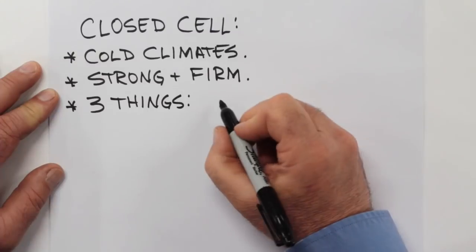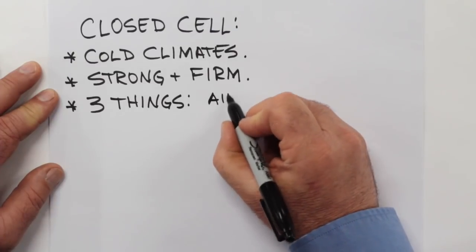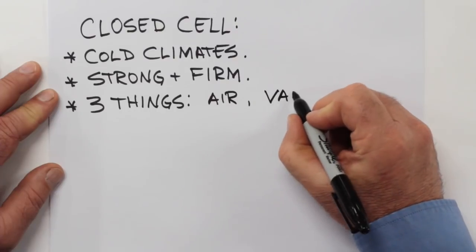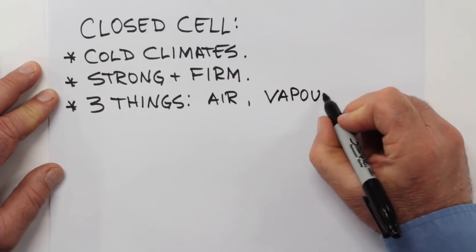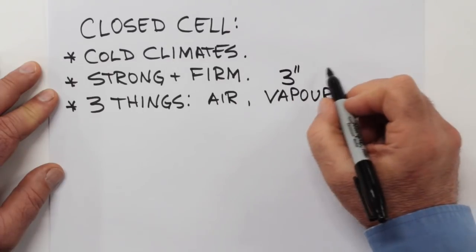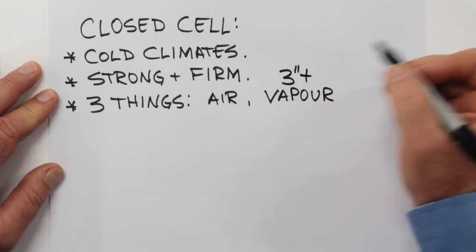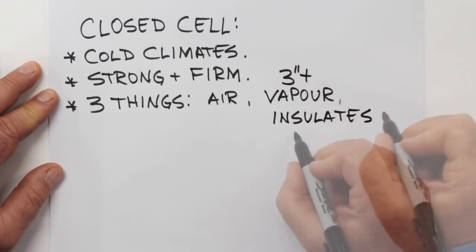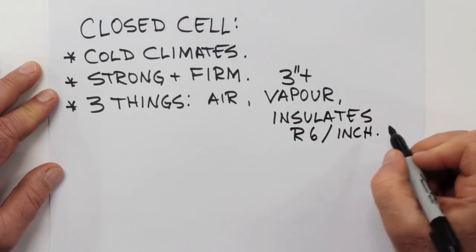Closed cell also does three things well. First, it blocks air movement exceptionally well. Second, it blocks the passage of water vapor. That's the quality that separates it from open cell, as long as that closed cell is applied three inches thick or thicker. And of course, closed cell does deliver exceptional insulation properties as well, about R6 per inch.